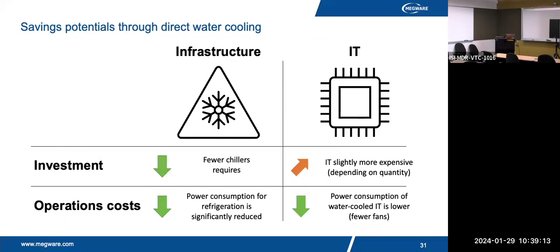Of course, in terms of investment, the IT is slightly more expensive because you have to hook up the water cooling on top of it. But over time, the price goes down, and you have less power consumption, so you need less dollars for that. If you take the chillers, you also require fewer chillers. On average, you require one seventh of the chillers you need for air cooling, which is also already an investment and it's cheaper. Over the operation, the power consumption goes down and you need fewer chillers. So this really shows that hot water cooling is competitive.